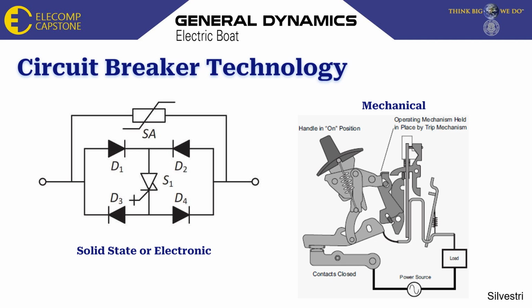Another big difference is that solid state circuit breakers, as the name implies, are one piece. There are no moving parts, no connections that physically open and close like a mechanical circuit breaker. Because our system relies on being rugged, able to take vibration and movement, as well as reliable with a fast response time to outages, solid state circuit breakers are the technology we moved forward with and are going to implement into our system.